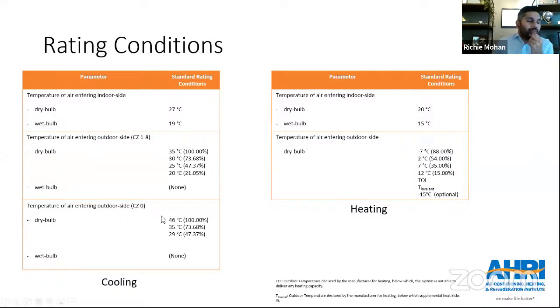But from climate zone 0 perspective, it usually becomes a problem, because if your full load testing is happening at 35 degrees Celsius, you're basically extrapolating that data to come up with 46 degrees Celsius to see what might happen in the heat. Is that really an accurate representation, or the method that needs to be used for getting those ratings and verifying them? That's where people are a bit skeptical about just having climate zone 0 conditions fed under climate zones 1 through 8.